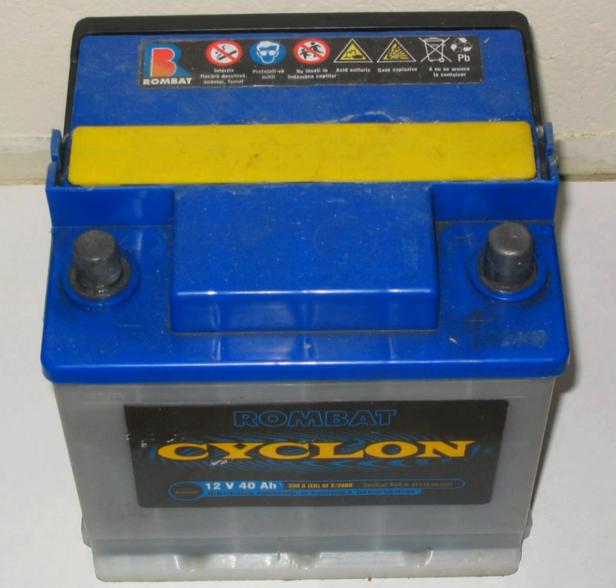Corrosion of the external metal parts of the lead-acid battery results from a chemical reaction of the battery terminals, lugs and connectors. Corrosion on the positive terminal is caused by electrolysis, due to a mismatch of metal alloys used in the manufacture of the battery terminal and cable connector. White corrosion is usually lead or zinc sulfate crystals. Aluminum connectors corrode to aluminum sulfate. Copper connectors produce blue and white corrosion crystals. Corrosion of a battery's terminals can be reduced by coating the terminals with petroleum jelly or a commercially available product made for the purpose.